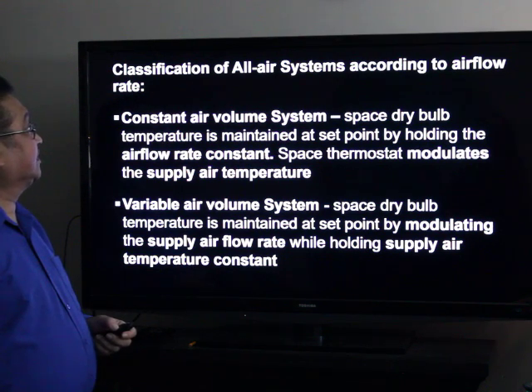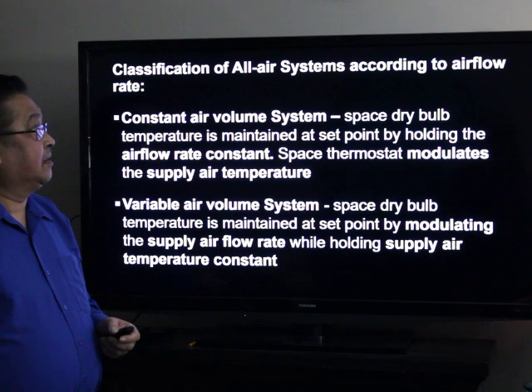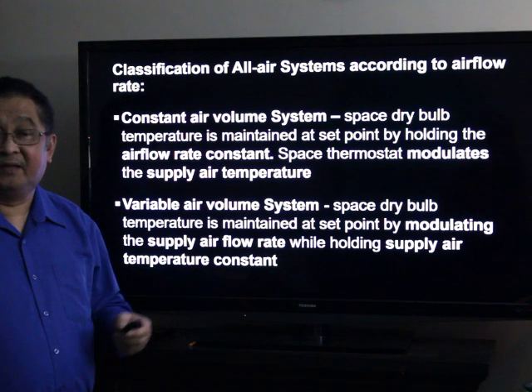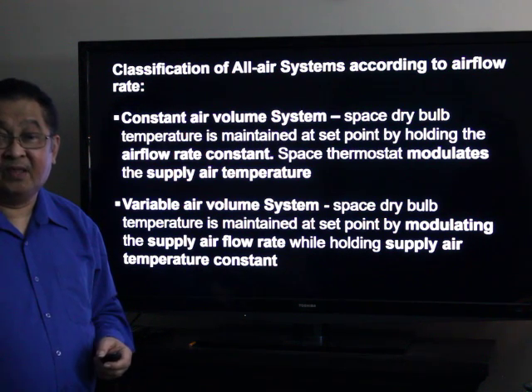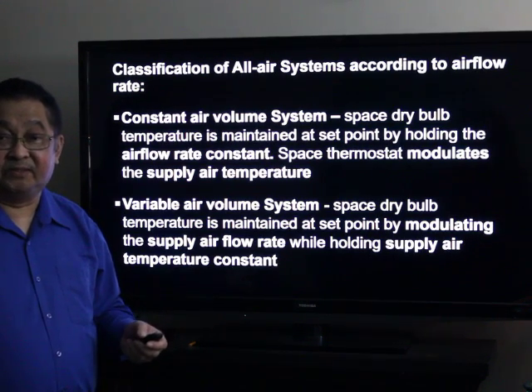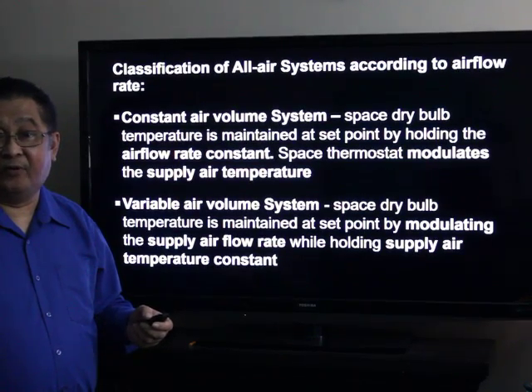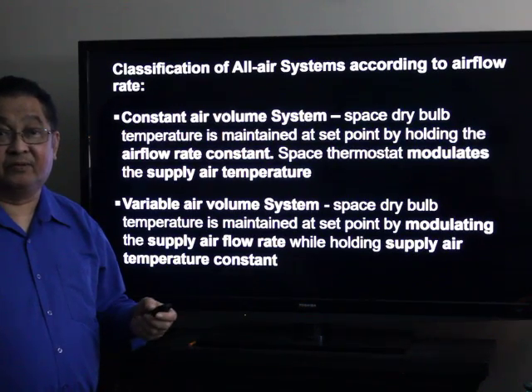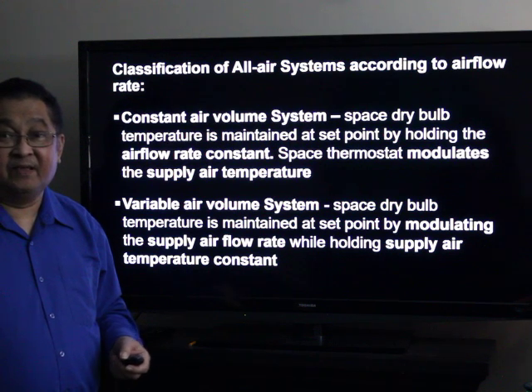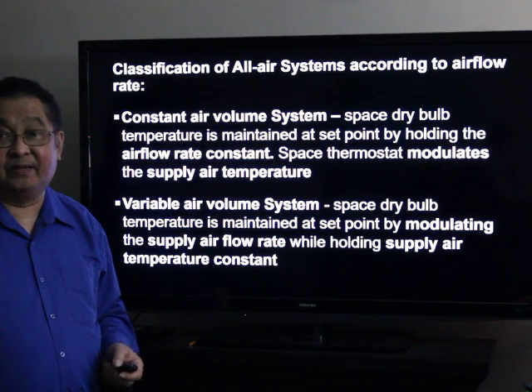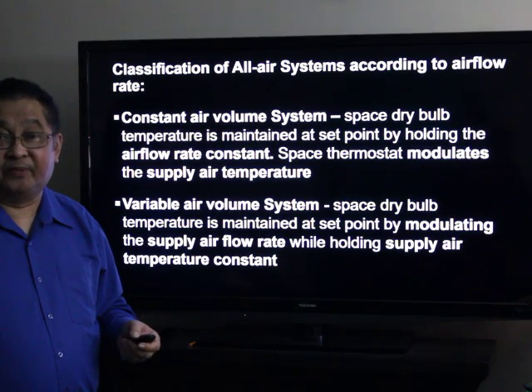There are two classifications of all air systems according to the air flow rate. The first one is the constant air volume system. And the second one is the variable air volume system. For the constant air volume system, the set point temperature of the space is maintained by holding the air flow rate constant while modulating the supply air temperature. For the variable air volume system, the set point is maintained for the space temperature by holding the supply air temperature constant and modulating the air flow rate.